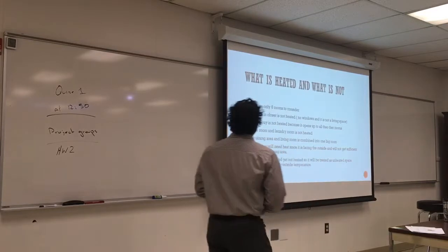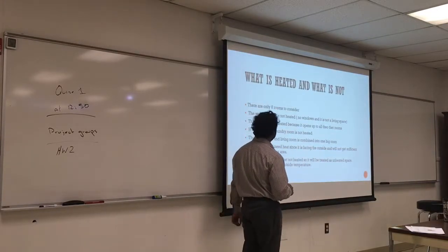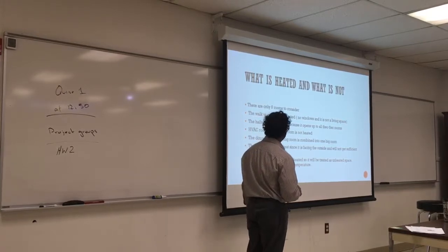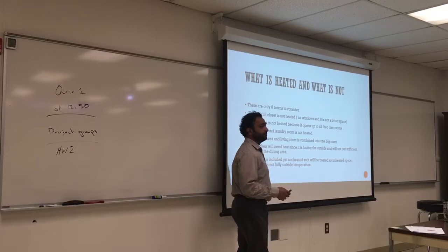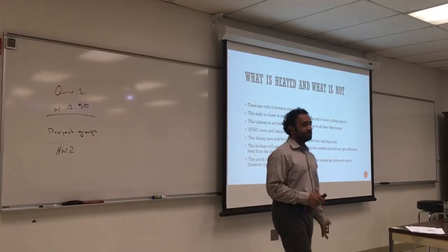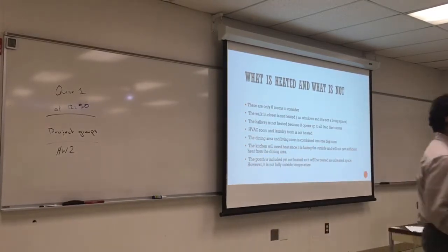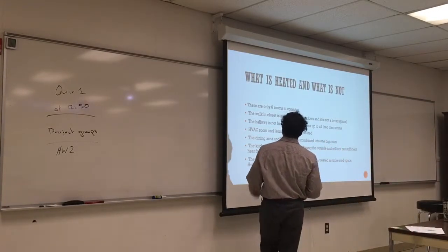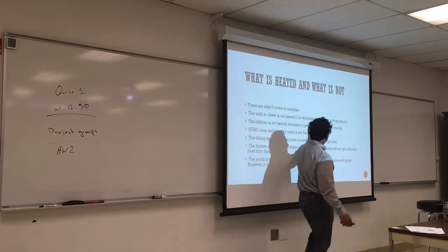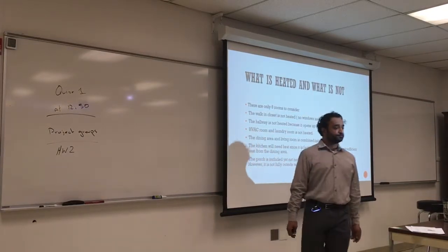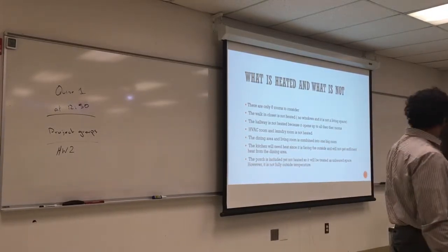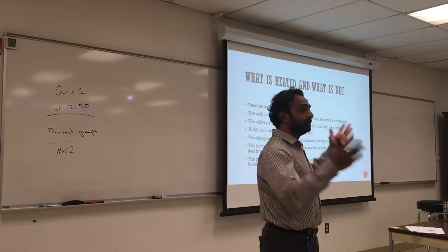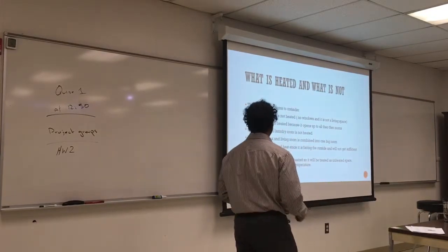So, what is heated and what is not heated? There are only six rooms to consider in this project. The walk-in closet is not heated because there are no windows and it's not a living space. You don't care if the closet is cold, and usually the closet has a door. If it's a walk-in, no need to heat it. The hallway is not heated because it is open to all the other rooms. So we're not going to put a heater in the hallway because the other rooms will be heated and will dump heat into the hallway.